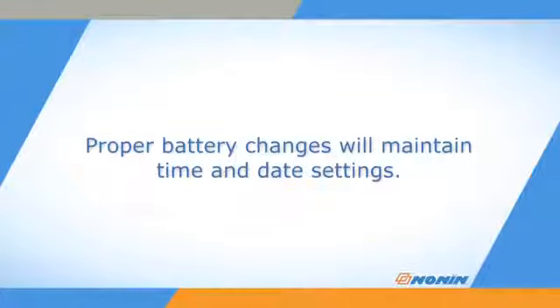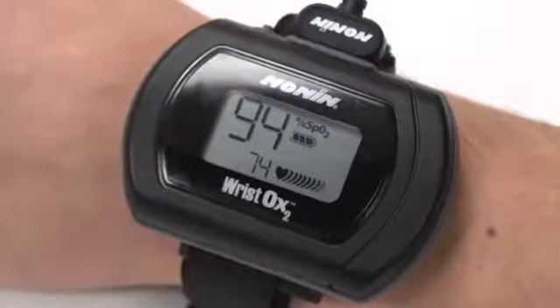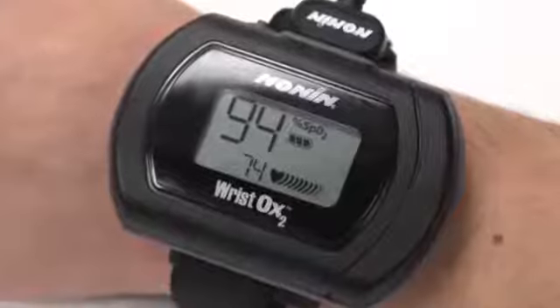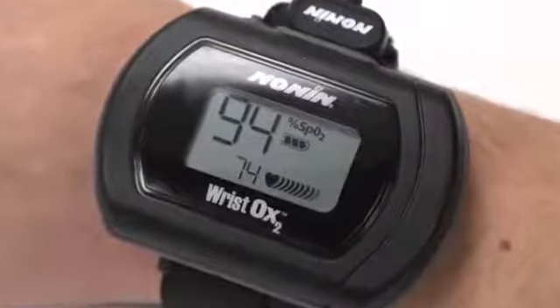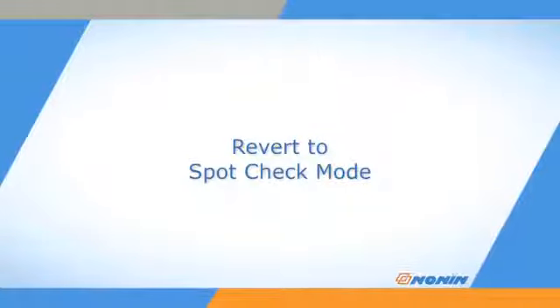If the oximeter has been in use and had regular battery changes or recharges, the settings should be retained in the oximeter for its next use. The battery charge indicator on the display shows full, half, low, and critical levels. The oximeter will revert to spot check mode only when the device is at the critical battery level. Date and time settings may be lost if the oximeter is used at the critical low battery level for an extended period.